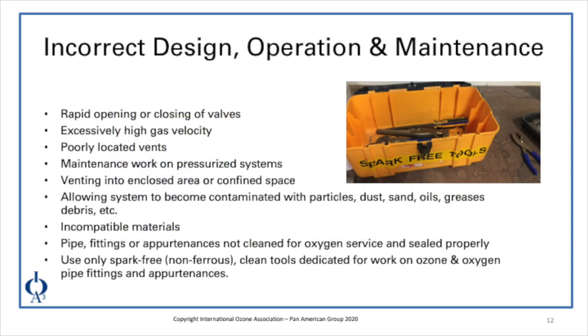A few things to avoid regarding incorrect design, operation, and maintenance of oxygen systems: avoid rapid opening or closing of valves, which can lead to pressure swings and ultimately create an ignition source. Avoid excessively high gas velocities and poorly located vents. On liquid oxygen systems, don't trap liquid between two closed valves without a potential to vent, because as that liquid heats up, it's going to expand and may ultimately lead to bursting the pipe or leaks on flanges as that pressure rises.